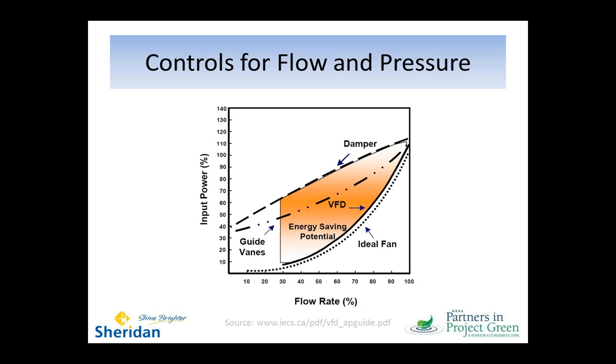That said, this isn't a universal claim that everything should be controlled by a variable frequency drive. In this case, what we can see almost straight away is that if our application is somewhere between 100% flow rate and maybe 85% flow rate, the actual difference in input power over that span, even at 85%, is maybe 15–20% of input power levels. We may find in that case the extra cost of the variable frequency drive versus a damper just doesn't make sense, and you can't make the case.